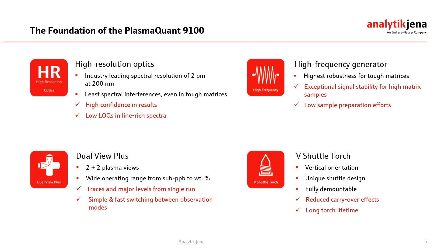The four key features of the instruments are shown here. We have integrated high resolution optics in these systems. With the aid of these optics it is possible to resolve even severe spectral interferences, which results in the lowest detection limits and highest confidence in obtained results. We have also integrated a high frequency generator with exceptional matrix tolerance, and we provide a dual view plus option which allows for a wide operating range — measuring elements from the sub-ppb up to the percentage range in a single run. We have also included a unique shuttle design which allows for high operator comfort and provides long torch lifetime. In the following I will explain these features in more detail so that you get an idea how you can benefit from them for your particular application.